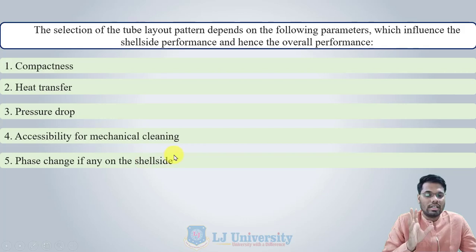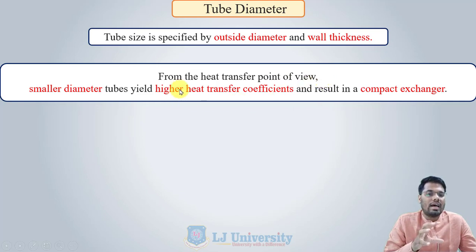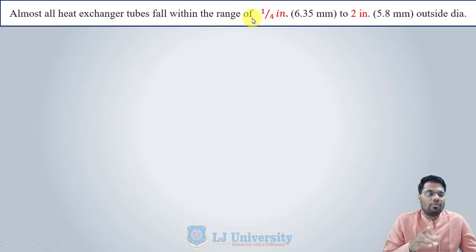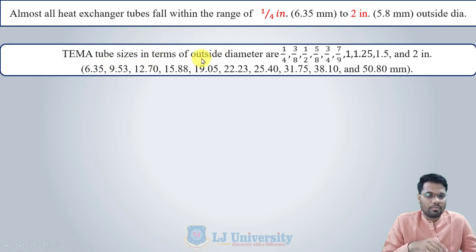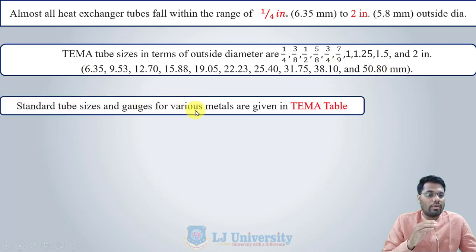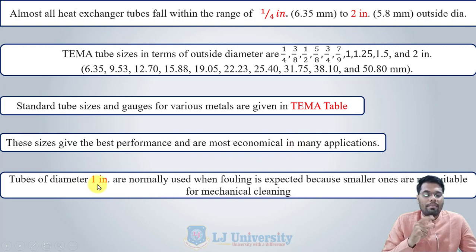Tube size is specified by outside diameter and wall thickness. From a heat transfer perspective, smaller diameter tubes yield higher heat transfer coefficients and result in a more compact heat exchanger. Larger diameter tubes are easier to clean, more rugged, and necessary when allowable tube side pressure drop is small. Almost all heat exchanger tubes fall within the range of 1/4 inch (6.35 mm) to 2 inch (50.80 mm) outside diameter. TEMA standard sizes range from 6.35 mm to 50.80 mm, giving the best performance and most economical results in many applications.